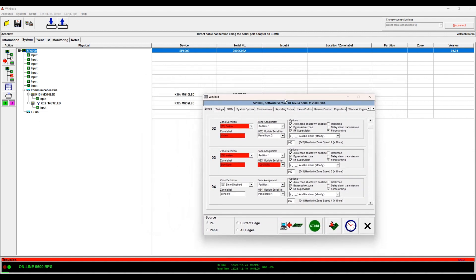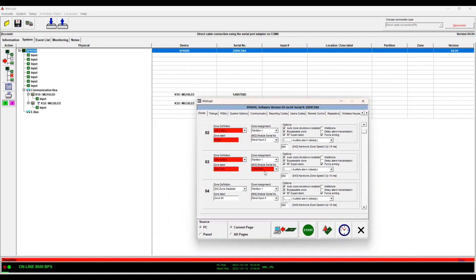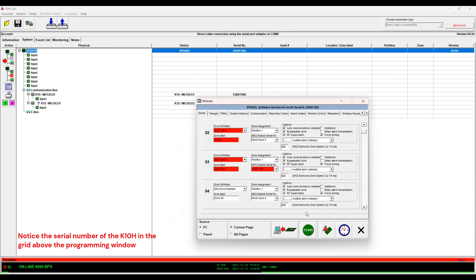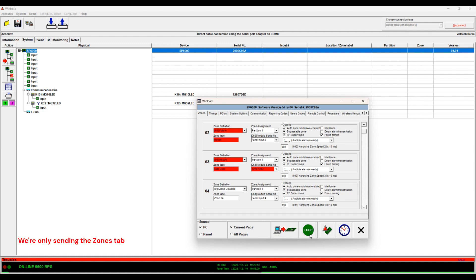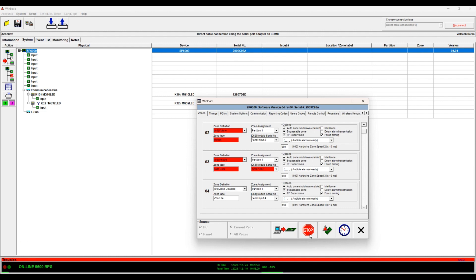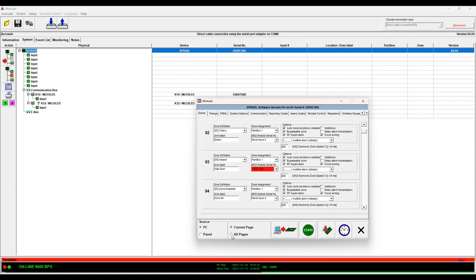So the K10H is this, I believe. Let's see, K10H, yes this is it. So I select it and then once I'm done, that's done. I'm done with this programming, the two zones that I have on the system. So I can see here it says PC to panel or panel to PC. So you click like this to send from the PC to panel, and then I only want to send the current page. Then click Send and now my zones should be programmed. Once they are programmed, all the reds are going to go away. If you're doing multiple changes on all the pages, then you would need to select all pages, but because I only programmed one page, I only select current page.